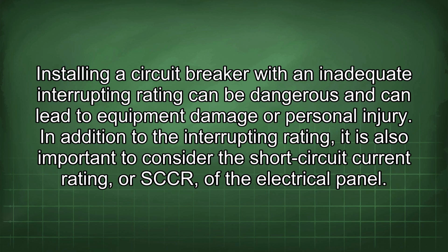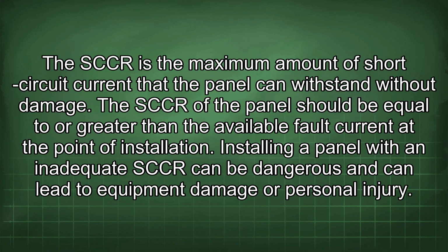In addition to the interrupting rating, it is also important to consider the short circuit current rating, or SCCR, of the electrical panel. The SCCR is the maximum amount of short circuit current that the panel can withstand without damage. The SCCR of the panel should be equal to or greater than the available fault current at the point of installation. Installing a panel with an inadequate SCCR can be dangerous and can lead to equipment damage or personal injury.